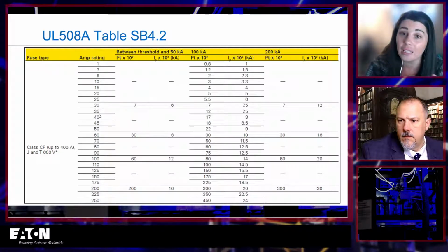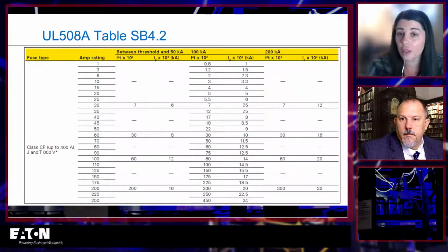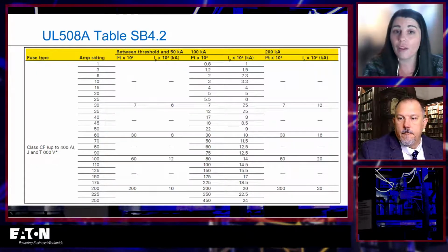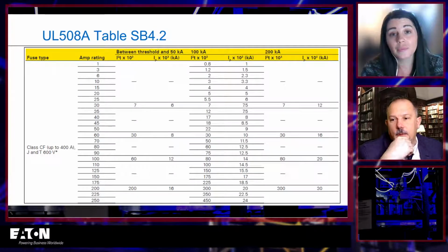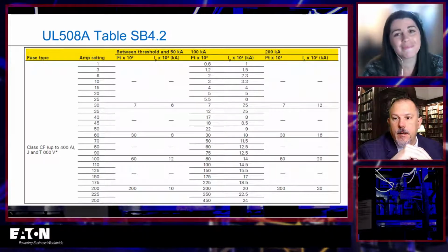And we use peak let-through here. So it's not the RMS let-through of a fuse, it's the peak let-through. It's a higher value. That's what you have to use according to UL 508A. So, to repeat what I said about not being able to use a current limiting fuse to raise the SCCR of a piece of equipment or component.